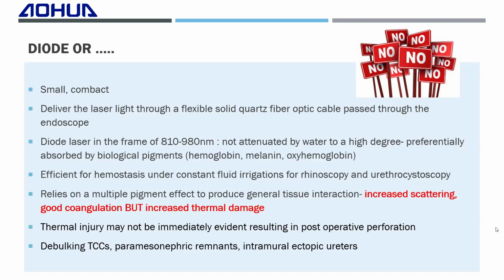So if you are doing interventional endoscopy, why use the laser or the EHL if they will probably damage the endoscope? Okay, Nir, it's not that they will damage the endoscope. If your fiber fractures in the endoscope, then they will damage the endoscope. This is one thing. And the second thing is that you have to keep a distance from your scope lens. If you keep a distance from your scope lens of at least 3 millimeters, then you don't have a problem. It will not damage it.